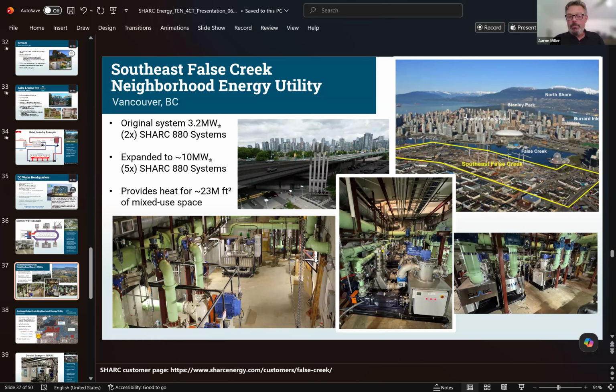It was so successful that they recently ripped out these two older units. They're working perfectly fine, but they were like, hey, let's step it up. And we've now, about almost 9 months ago, commissioned five SHARC 880s. We're now filtering over 6,000 gallons of raw sewage every minute. We're taking that filtered sewer water and pumping it into these ginormous York YTK 3 megawatt heat pumps to make 180-degree hot water that we then pump around downtown Vancouver.